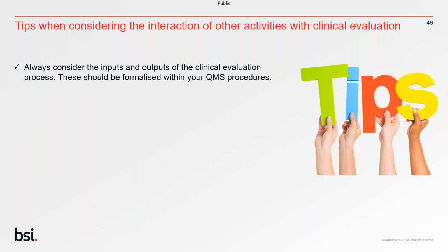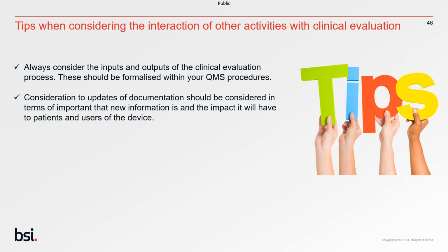So always consider the inputs and outputs of the clinical evaluation process. These should be formalized within your QMS procedures. Updates of documentation should be considered in terms of important new information and how impactful it is to the patients and users of the device.